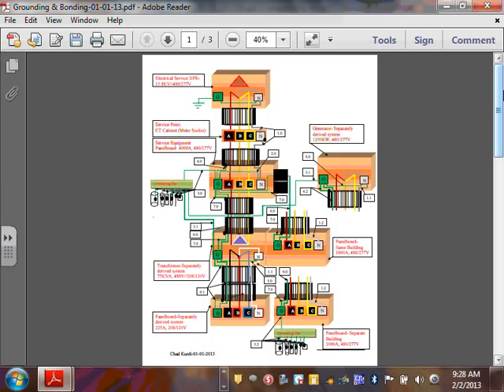When the panels are inside the same building, there are rules and regulations for bonding and grounding, as all of you probably know. Then I took another feeder and fed another panel, also a sub-panel, but this sub-panel is in a separate building. So you have building A, a 4,000 amp switchgear, feeding building B with another 2,000 amp switchboard or switchgear. Or it could be a 200 amp residential 240/120 panel feeding a 60 amp panel in your detached shed, detached garage, or detached structure. This is what we call a separate structure or separate building.